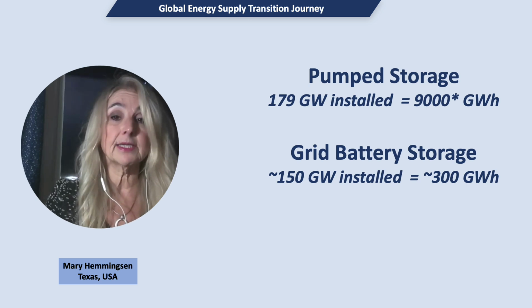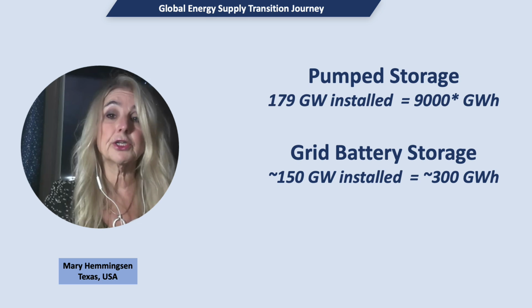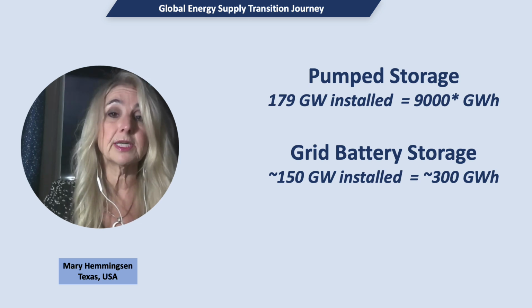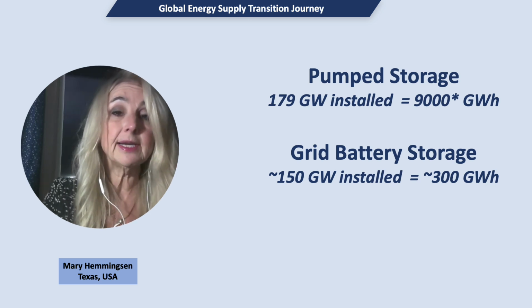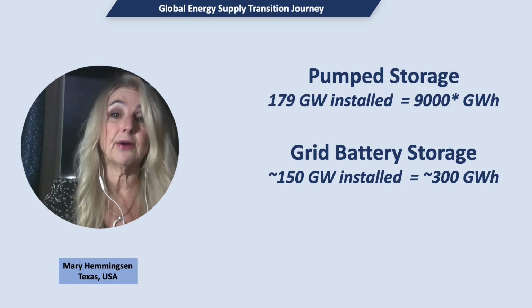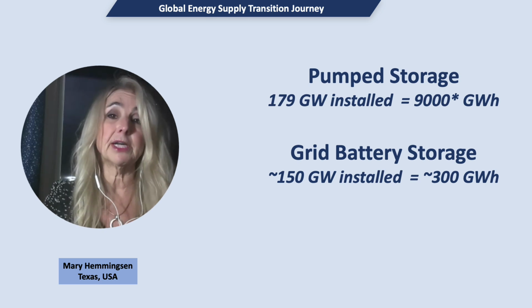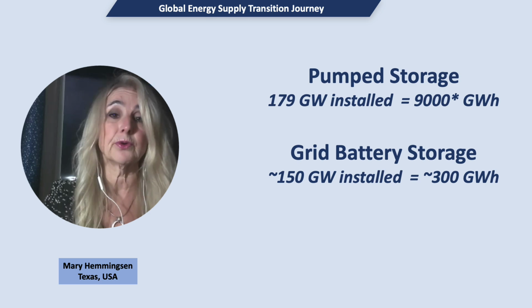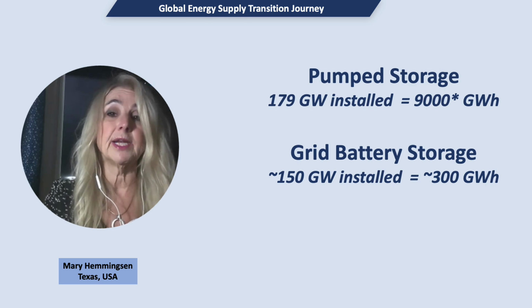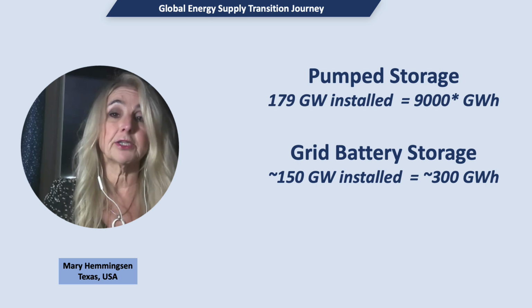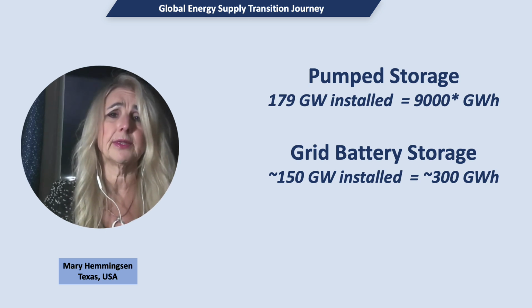179 gigawatts is the installed pump storage globally, which according to the International Hydropower Association has storage capacity of 9,000 gigawatt hours. However, in checking the reported figures, dividing 9,000 gigawatt hours by 179 gigawatts yields 50 hours of storage per 1,000 megawatts of generating capacity. This seems much higher than actual individual pump storage plants' hours of duration, ranging in the 20 hours plus or minus. So we suspect some considerable hydro reservoir storage is included in the total.